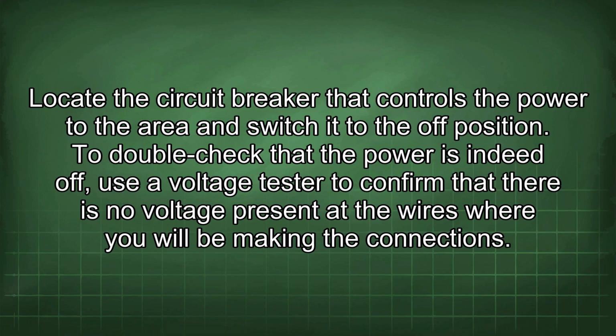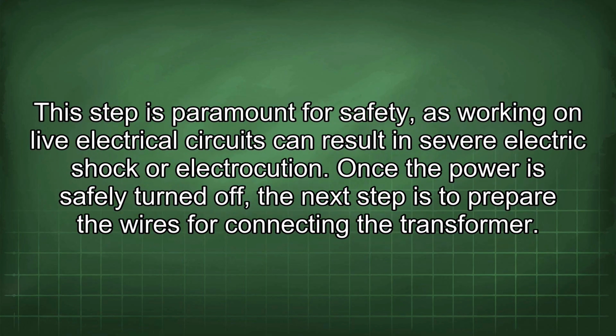To double check that the power is indeed off, use a voltage tester to confirm that there is no voltage present at the wires where you will be making the connections. This step is paramount for safety, as working on live electrical circuits can result in severe electric shock or electrocution. Once the power is safely turned off, the next step is to prepare the wires for connecting the transformer.